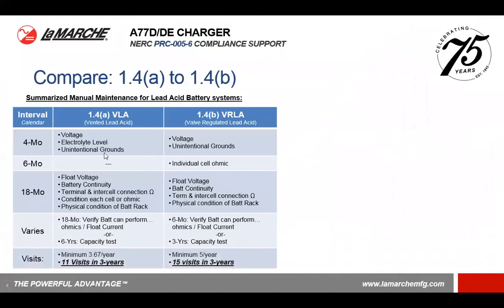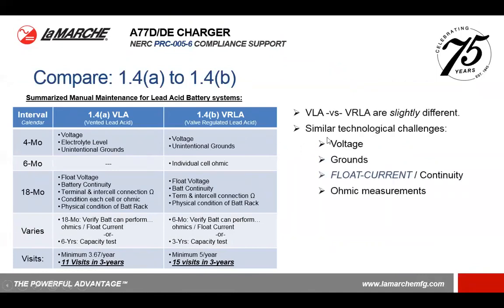I've put this table together to essentially compare the vented lead acid and valve regulated lead acid maintenance schedules. At 4 months, you're checking voltage and unintentional grounds. Ultimately, these tables are pretty similar, but there are some slight differences. The slight differences really fall in not having an electrolyte level to check on VRLA, or individual ohmics on the VRLA do not apply to the VLA. But ultimately, the technological challenges are very similar. We have to evaluate for voltage, grounds, float current continuity, and ohmic measurements.